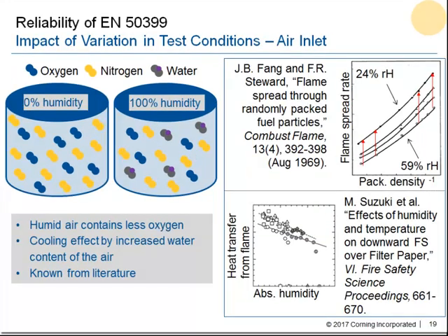The next is the ventilation, so the humidity of the air supply. Let's have a small dive into theory. On the left side, we see two containers with the same volume of air. One is with no humidity, the other one is with 100% humidity. For the 100% humidity, we have less oxygen and nitrogen present in the same volume of air, so less oxygen is present for the combustion. In addition, we have water molecules present, which might lead to cooling effects during combustion.